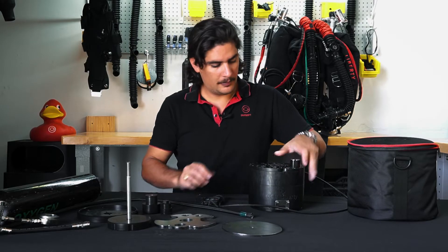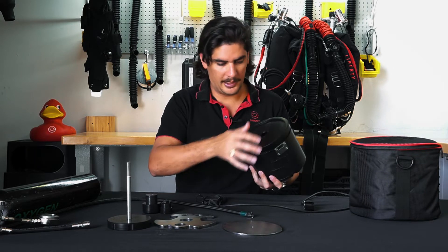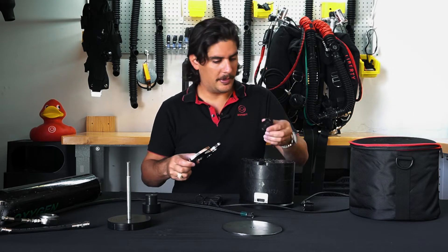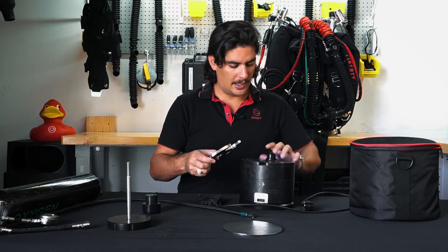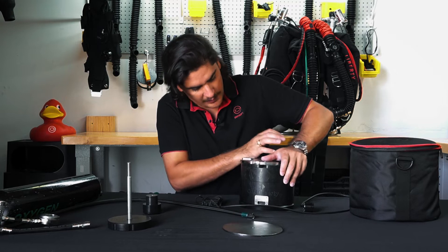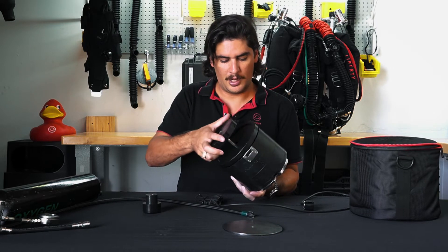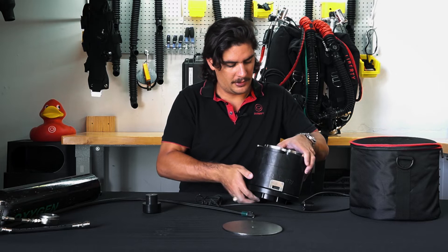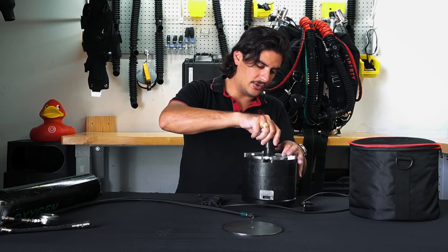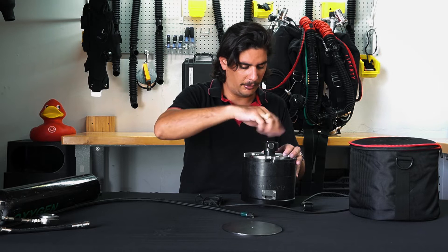To build it, I'm going to remove the handset. I'm going to take this base plate and plug it in here, and then this smaller piece goes into the inhale side. Then I take this plate and push it straight down, making sure everything's nice and flush. Then I'm going to take that bottom piece and screw the knob straight in here to the top. You can see that the plate needs to be held in. The Oxygen Cell Tester Kit basically creates a pressure system for the Liberty head — it turns the head into a pressurized chamber.